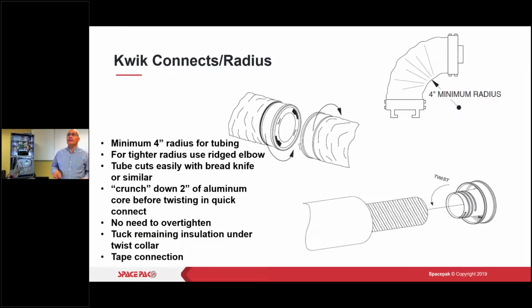So here's our quick connect. When we make those connections, it's the quick connects that we're going to go from our plenum, run our 2-inch, and then our sound attenuating tubing is going to click into that. And then we have our puck, or our escutcheon plate if you want to call it, sticking out or covering at the ceiling, wall, or floor. Okay, it's aluminum tubing. It's very easy to cut and bend and do whatever you have to do. You guys have a lot of experience with this. I really don't have to go into a tremendous amount of detail.